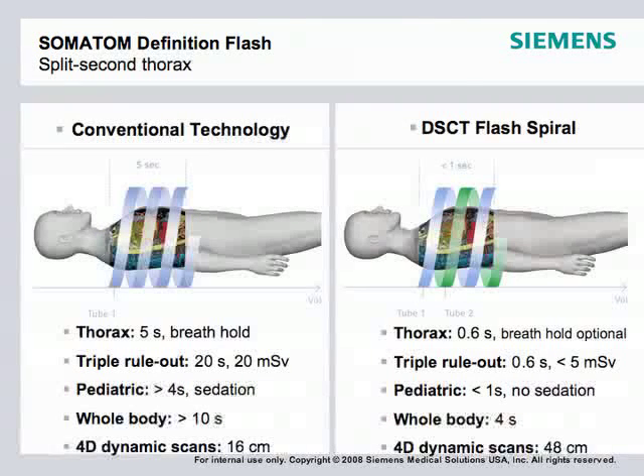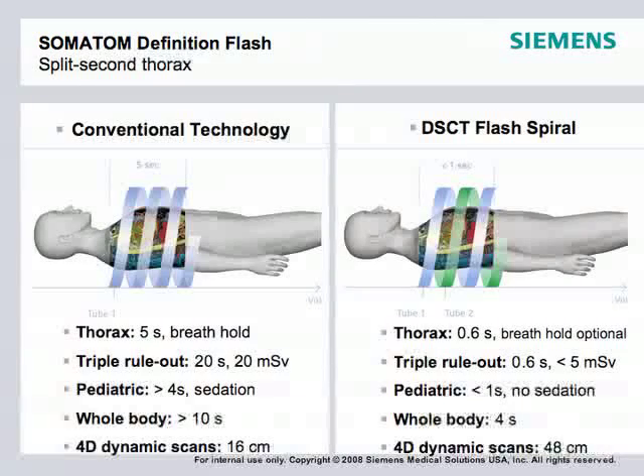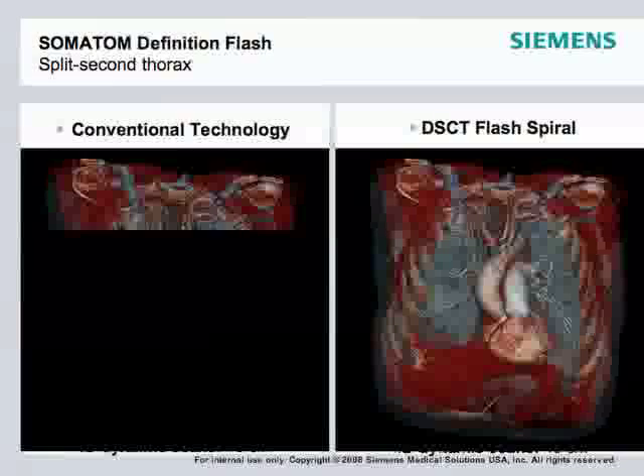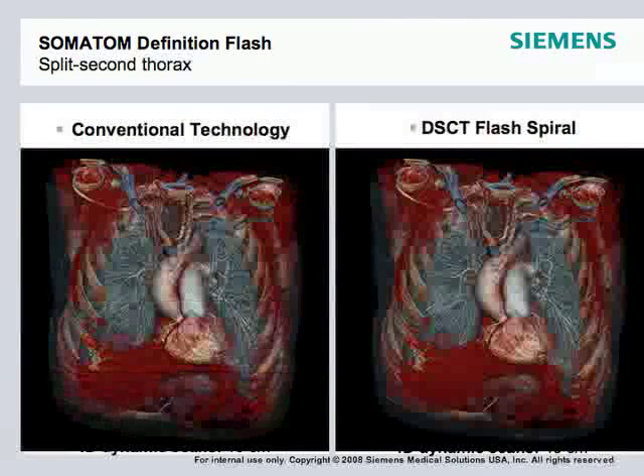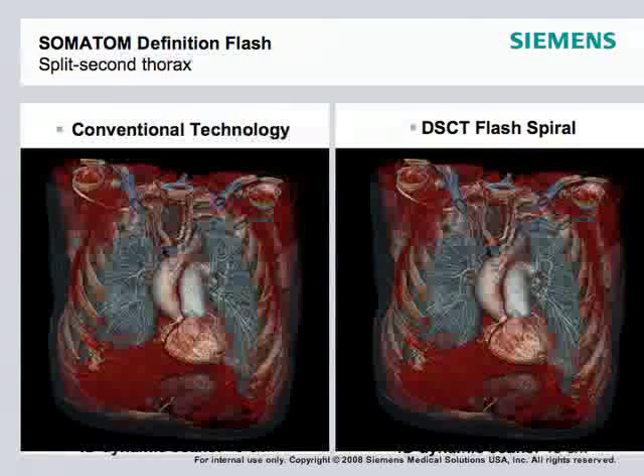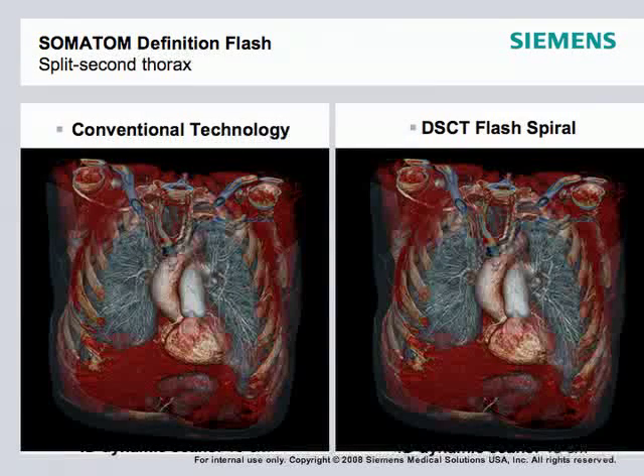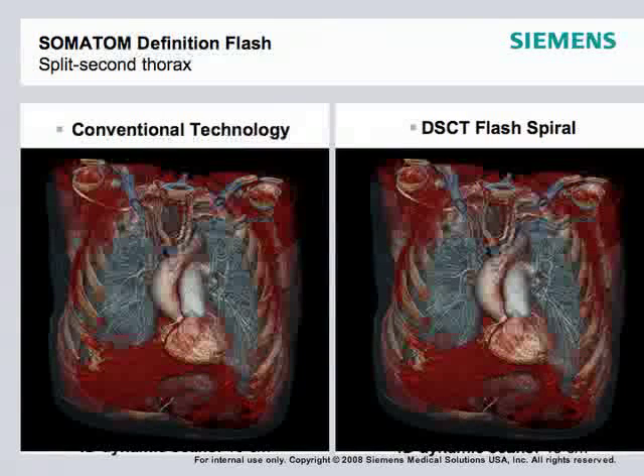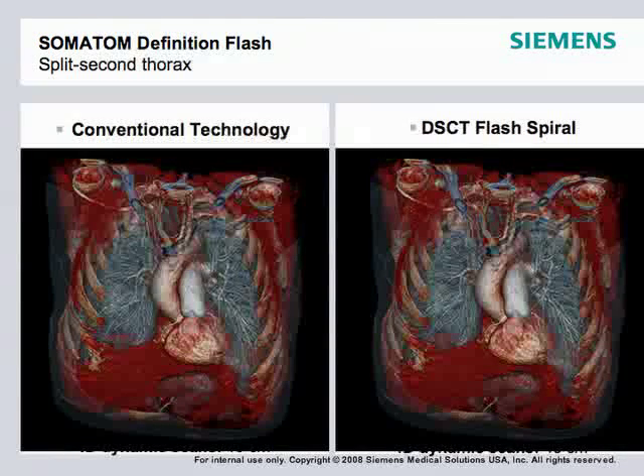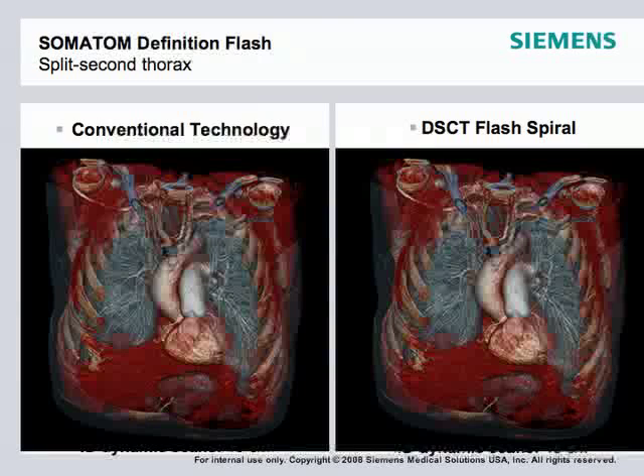At 0.6 seconds, the entire chest scan is completed — that's slightly longer than the blink of an eye. Currently, conventional scanning is around 20 millisieverts and 20 seconds for a total triple rule-out from top to bottom. With flash technology, we're able to do it in 0.6 seconds at less than 5 millisieverts — routinely around 3 millisieverts — for an entire triple rule-out exam covering the full chest from apex to base.